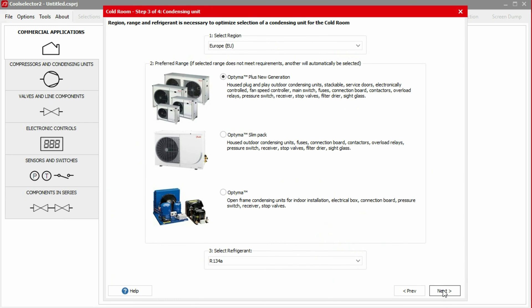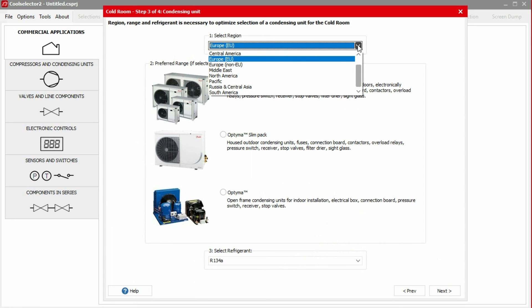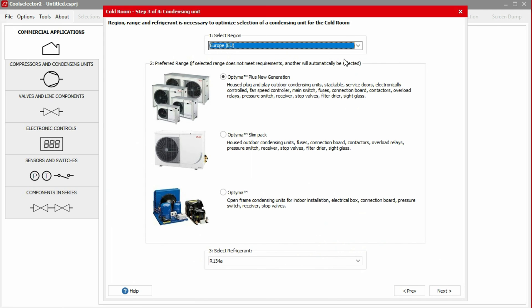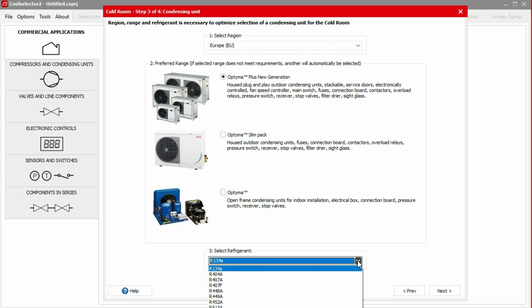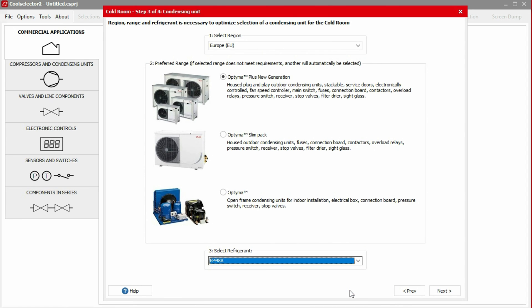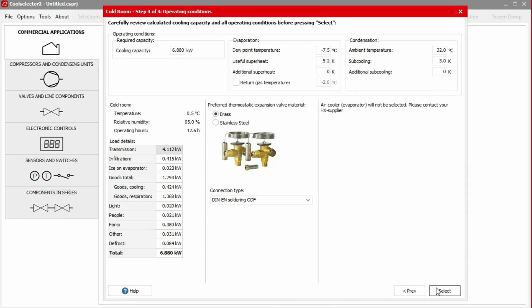We can now select a condensing unit for our cold room. We start by selecting the region of installation for the cold room. In this example, we'll choose Europe. We now need to choose which model of condensing unit to use. In this example, we'll choose the Optyma Plus new generation. At the bottom of the window, we choose the refrigerant. In this case, we'll select R448A from the dropdown menu, and then click next to continue.